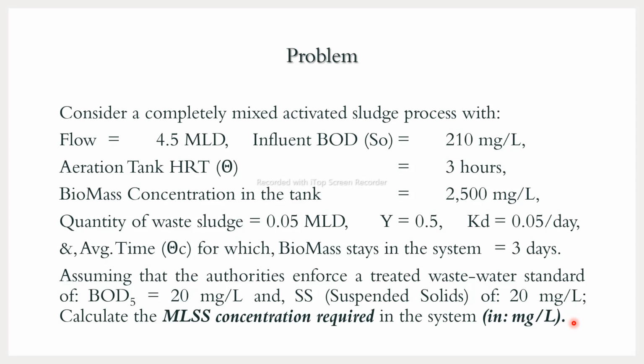Only the MLSS or MLVSS, the activated part, participates in decreasing the BOD and increasing their own number, right? The other parts of the SS, that is SS minus MLSS, whichever is left, don't contribute. That's why SS is not useful data here.